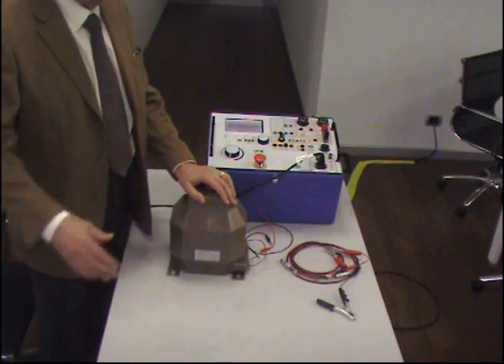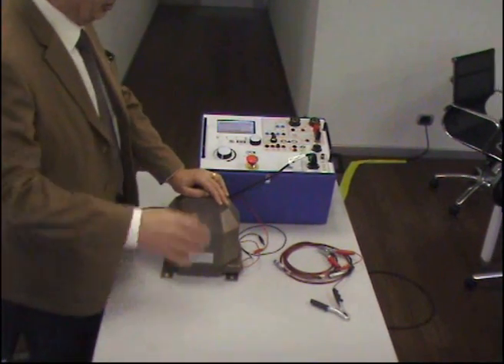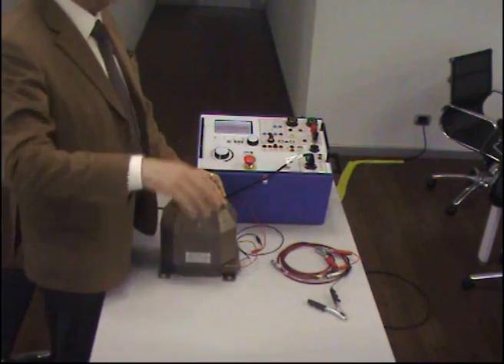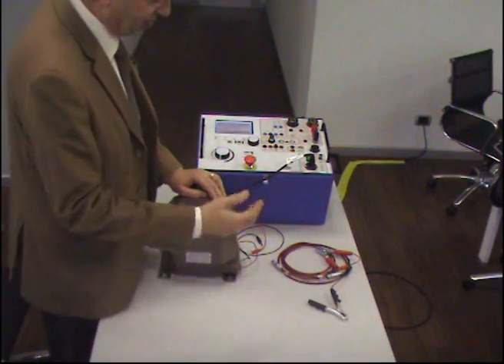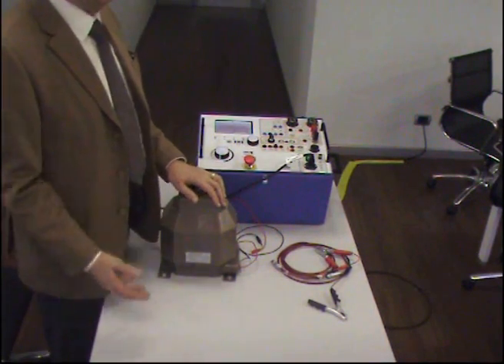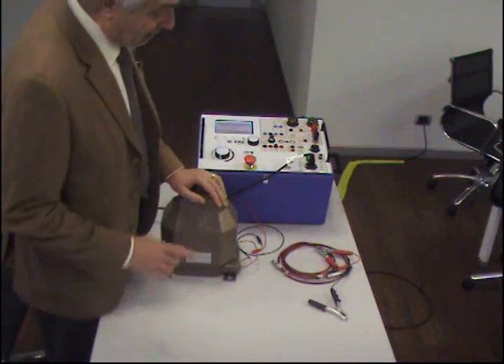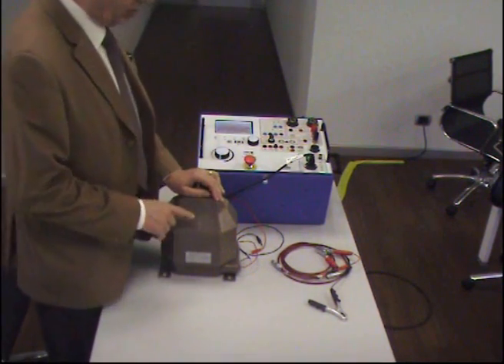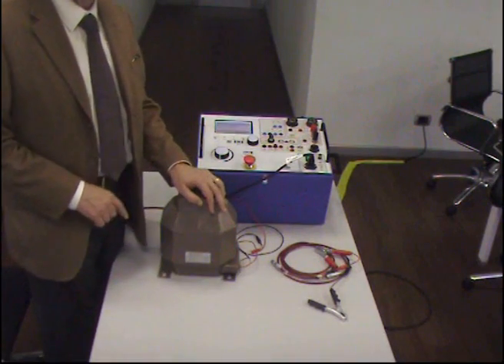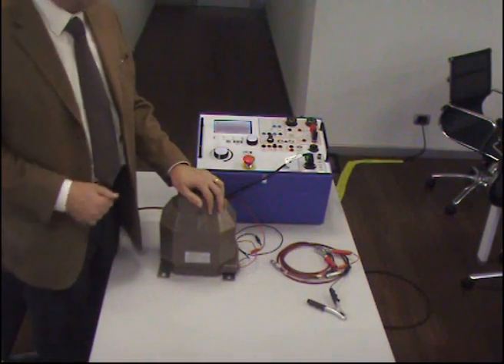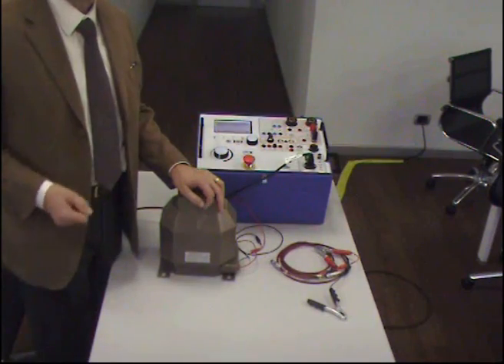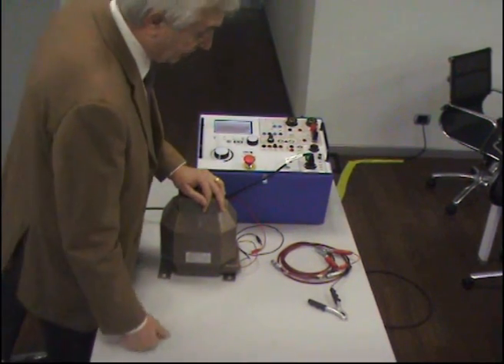Okay? You have many cables going from the transformer to the relays and everything, and these cables have to be isolated. Well, actually, one pole of the current transformer will be connected to ground, and that pole, of course, has to be removed prior to performing this test.